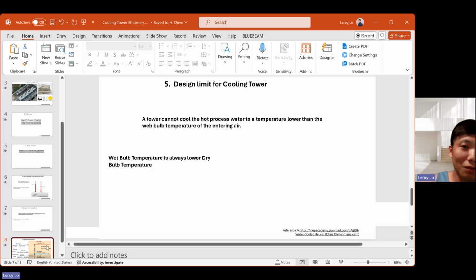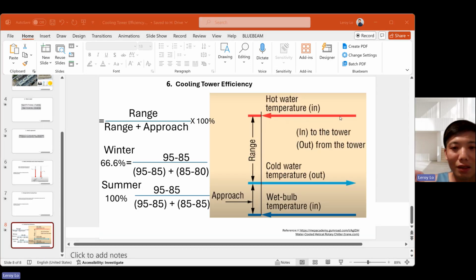For the calculation, this is very exciting now. For the cooling tower efficiency, as you can see in this diagram, starting from the top right side, hot water comes in from the hot process water into the cooling tower. In the middle, you can see the cold water temperature going back to the process cooling water. It's out of the cooling tower. The difference between the hot water and the cold water temperatures is the range. Now you can see the bottom side of the diagram, which is the approach: cold water temperature minus the wet bulb temperature. The cold water is the water coming out of the cooling tower, and the wet bulb temperature is that of the air coming into the cooling tower. So efficiency equals the range over the range plus approach, times 100%.